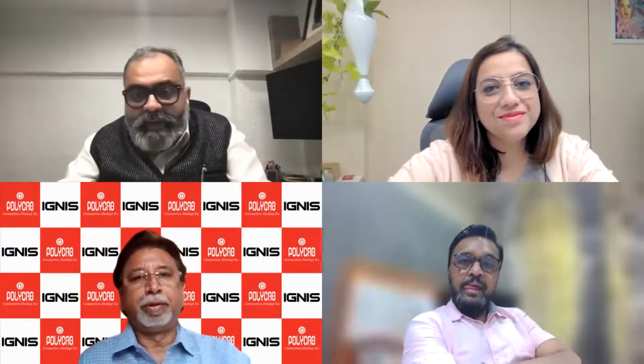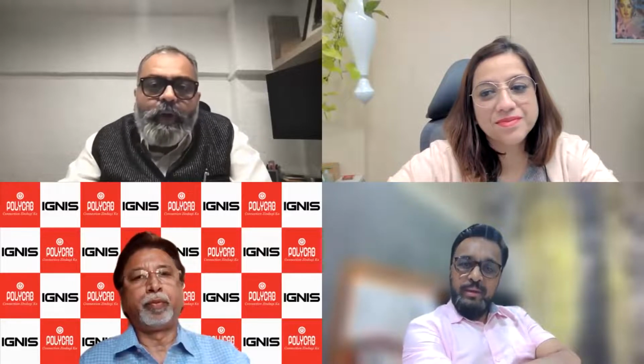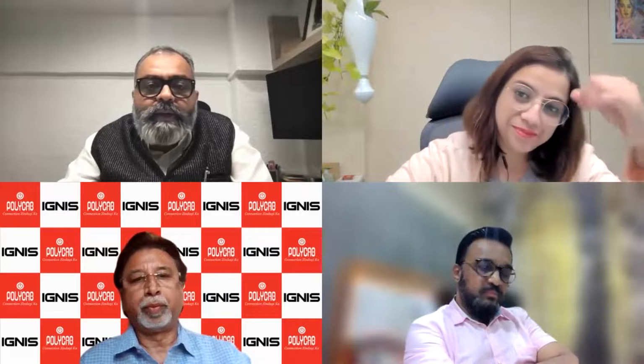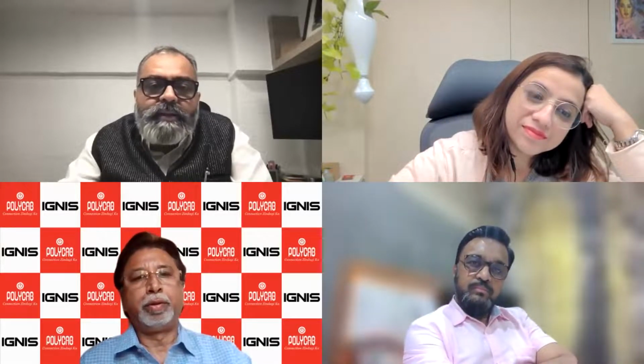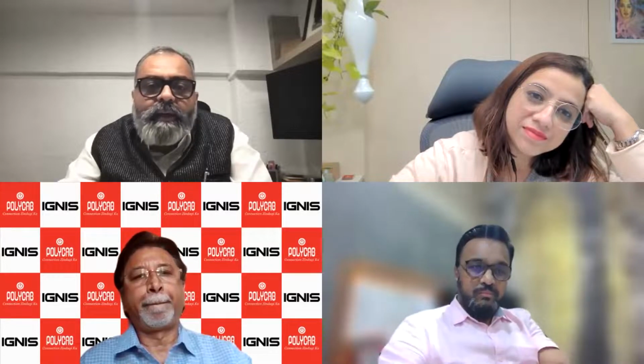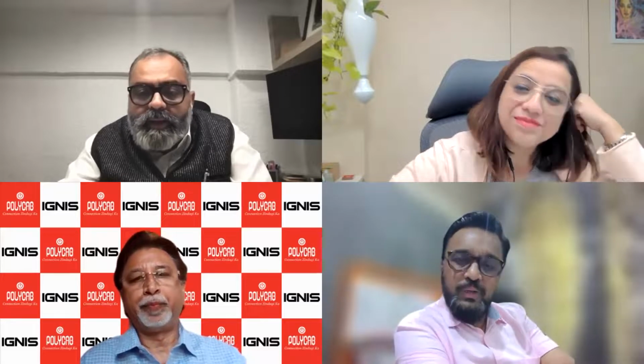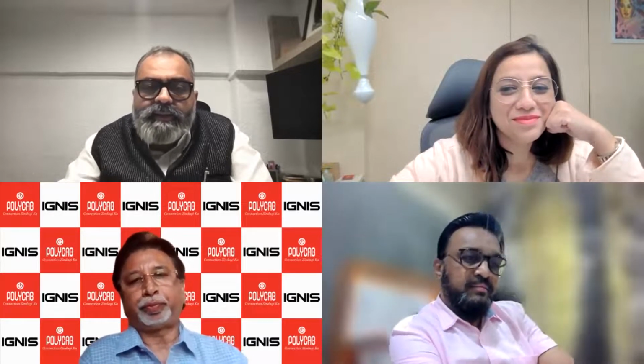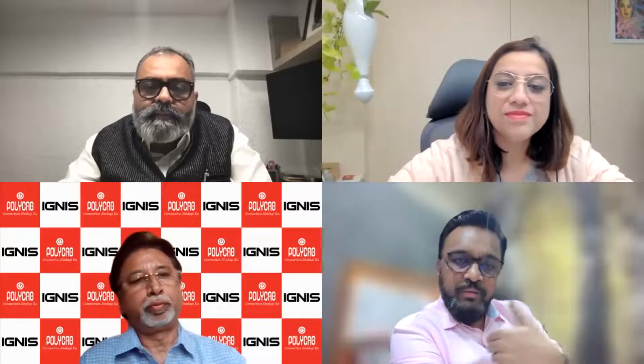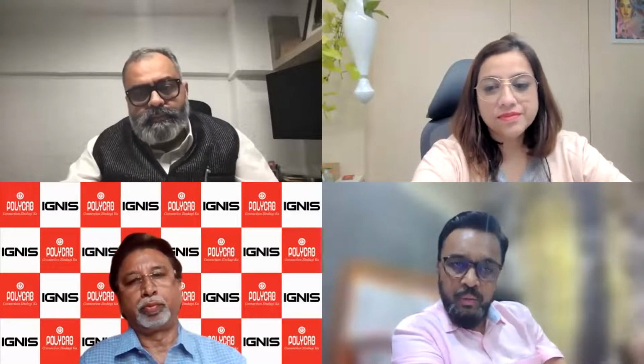Absolutely. And we have quite a few interesting questions here from many participants. There is one question from Mr. Amit Chiller, who says, does NBC give reference of the IS standard for cable selection? Absolutely. NBC is a document. It's like an International Building Code, or like NFPA 101, which says what is required. But for anything, when you say where it is required, it always gives a reference of the relevant IS code, and relevant IS codes are listed in the last 5-6 pages of NBC. So you always need to refer to an IS code. If NBC says you need to do a sprinkler system, how to do a sprinkler system? Of course, you have to refer to an IS code. That's understood. That's standard. You did not even ask that question.